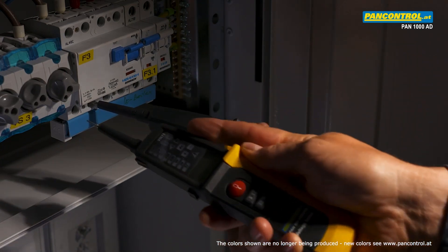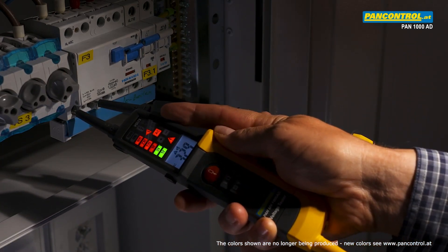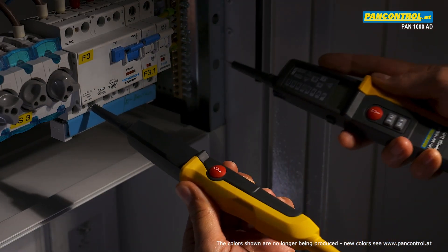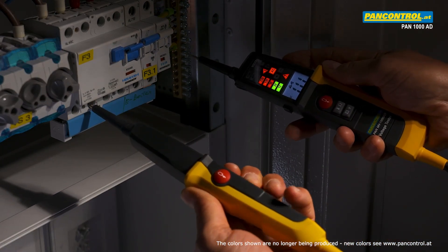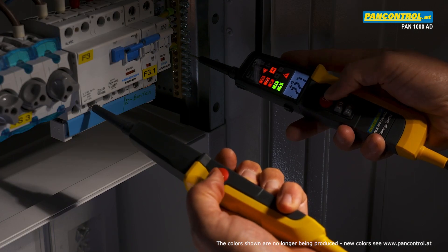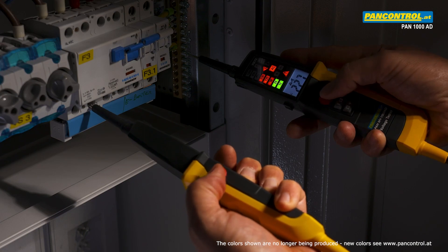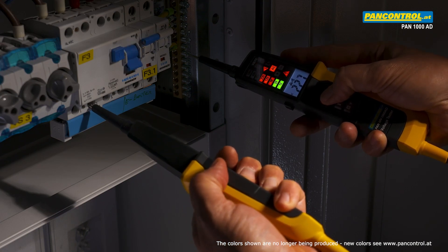After changing the two test tips, the rotary field indication changes to left field. During voltage test between the phase and the ground, the testing current can be increased to 30 milliamps by pressing both push buttons, such that the RCD switch can be tested.